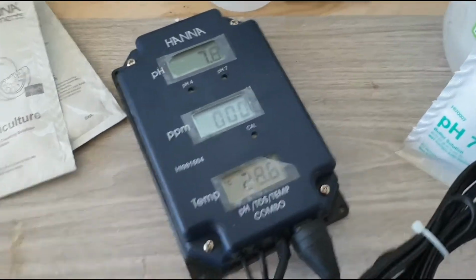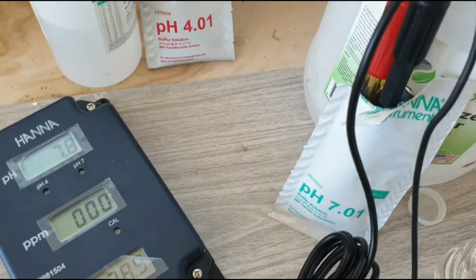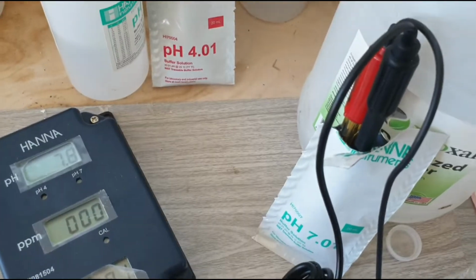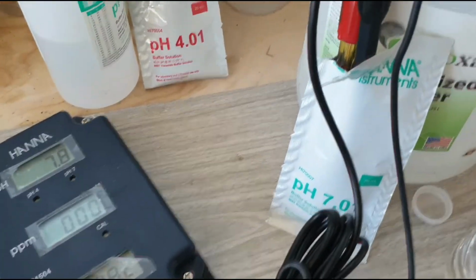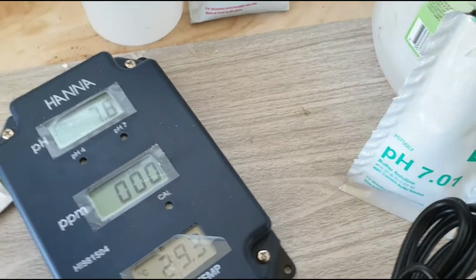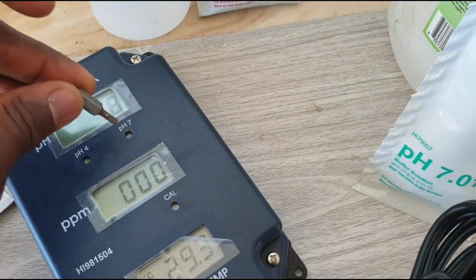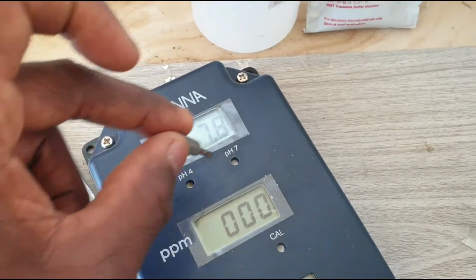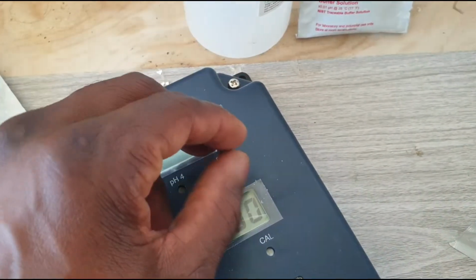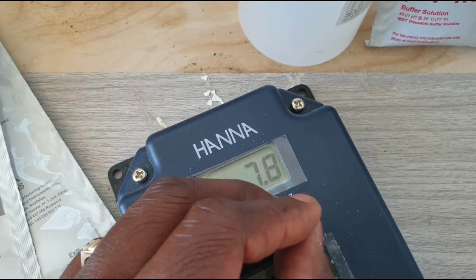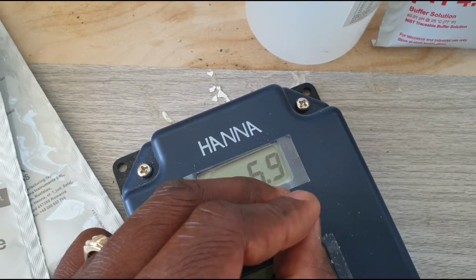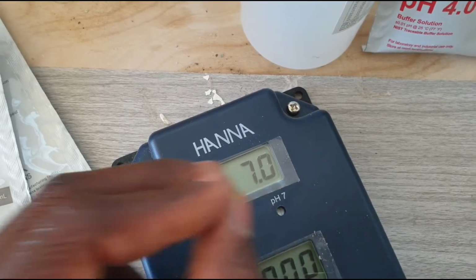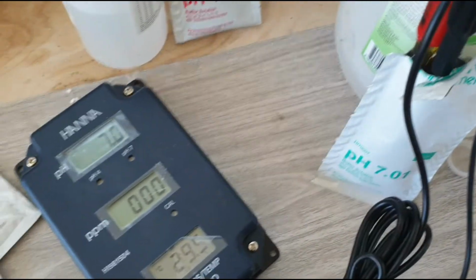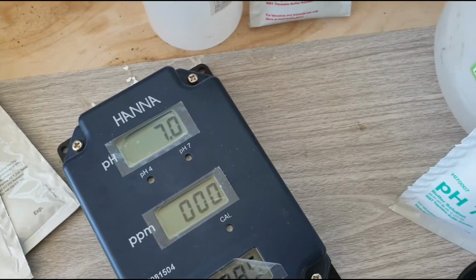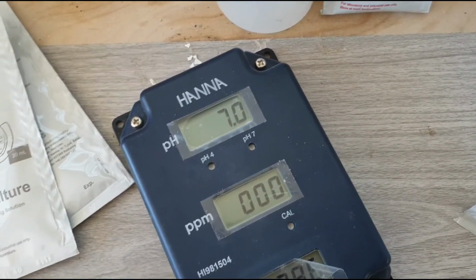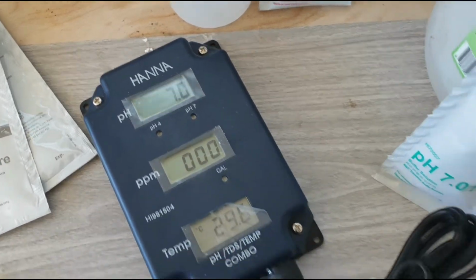So we dip the probe, the red one, which is the pH probe, along with the temperature probe, inside the pH 7 first. Then we're going to use this little tool here, and as you can see I have the pH 4, pH 7, so we go over on the pH 7 side and turn the knob until the value reaches 7.0, and allow it to stabilize a bit to ensure that it doesn't move. So that's it. pH 7 is calibrated.